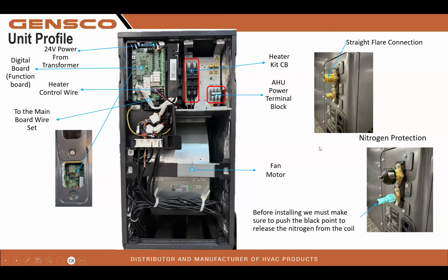This is a peek at our connections for our line set. Now, what is great about line set? Let's talk about line set real quick. All of our pieces of equipment from 2-ton to 5-ton air handler are going to use the same line set size: 3/8, 3/4. No 7/8, no inch and an eighth, nothing. It's 3/8, 3/4 for all tonnages.